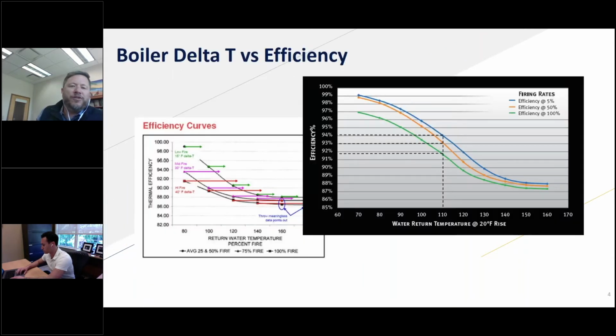So as we do that, we start looking at boilers and how we have traditionally designed boilers within a space. If we talk about the history of a boiler, and I'm not going to go too far into that, but if we just think about where we were 30, 40, whatever years ago, we would be looking at high temp boilers, right? So you're talking about 160, 180 degree hot water. And really, that's not necessarily something that was necessary for delivering heat into a space. There are lots of ways that we can deliver heat into a space with a much, much lower hot water temperature.